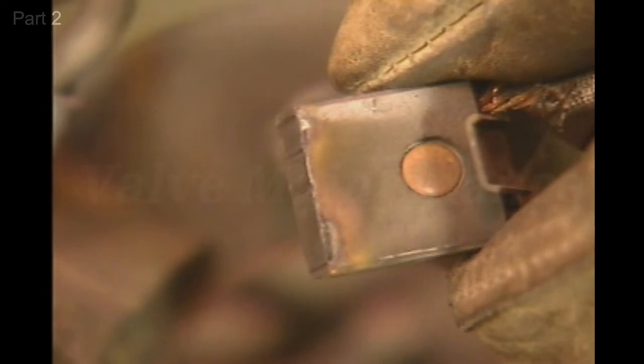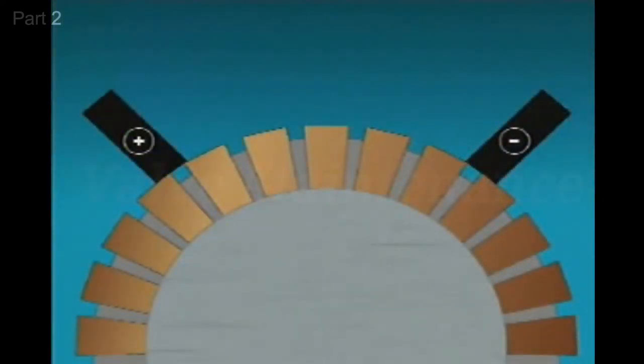When cracks or chips reduce the surface area of the brush, current has to flow through a smaller area. This may cause sparking or arcing between the brush and the commutator, and the brushes may heat up.